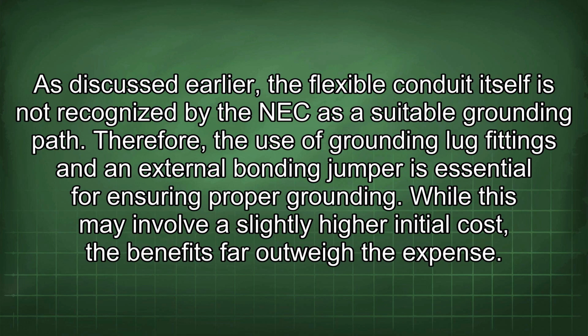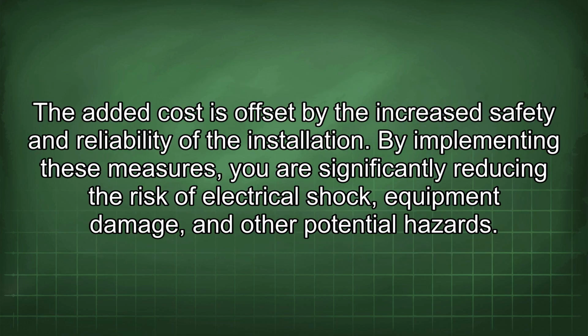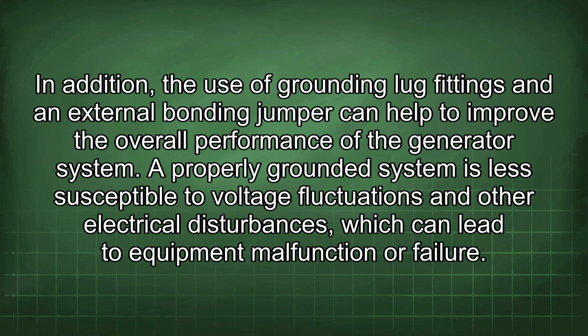While this may involve a slightly higher initial cost, the benefits far outweigh the expense. The added cost is offset by the increased safety and reliability of the installation. By implementing these measures, you are significantly reducing the risk of electrical shock, equipment damage, and other potential hazards. In addition, the use of grounding lug fittings and an external bonding jumper can help to improve the overall performance of the generator system. A properly grounded system is less susceptible to voltage fluctuations and other electrical disturbances which can lead to equipment malfunction or failure.